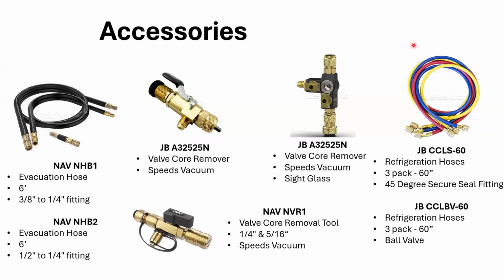So there's some options going, you don't have to, the old school days of throwing gauges on it, and going gaugeless is a better option. Get a micron gauge on right here, teed off of this, and then you can be recovering or watching the vacuum level right here. So vacuum here, and then you don't need a gauge set. So you're eliminating a lot of potential for leaks, etc. So refrigerant hoses. So again, just some extra tools there that are talked about.